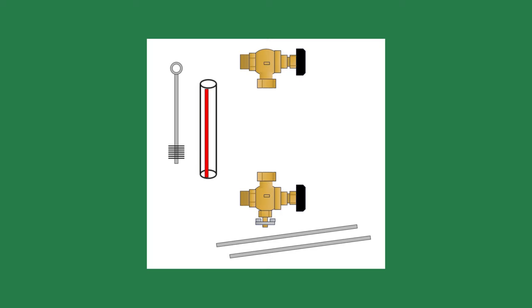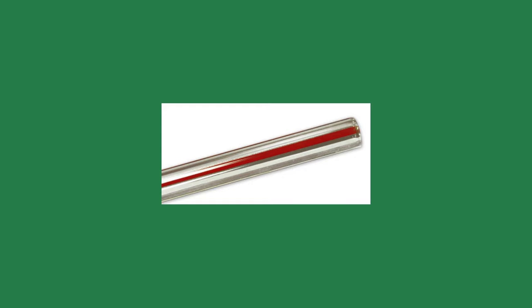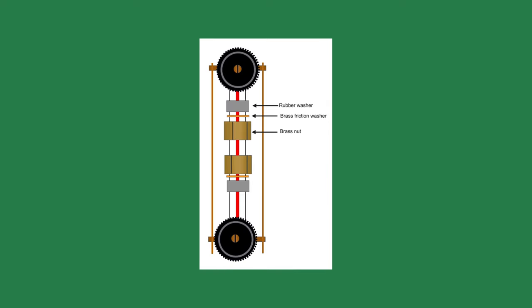Close the top and bottom brass valves so you don't get burnt, then remove the vertical brass rods on either side of the gauge glass. To size a replacement, measure between the top of the upper nut and the bottom of the lower brass nut — there is some space above the top nut to allow you to fit the gauge glass inside. I prefer the red-line gauge glass as it makes it easier to see the water line. When cleaning the gauge glass, be careful removing it as it could break easily. Take it to a slop sink, squirt some soap inside, and use small brushes — I found some at Harbor Freight. In the past I've used a straightened metal clothes hanger with a bit of paper towel wrapped around the end.